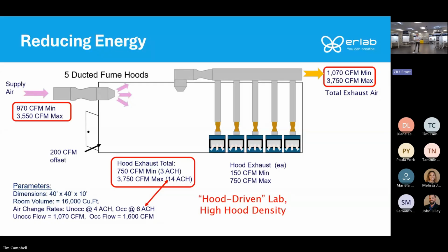When the sash is open, they're 750 CFM. You're going to have to design that lab space or your HVAC system to be able to have 14 air changes per hour when all those hoods are in use.